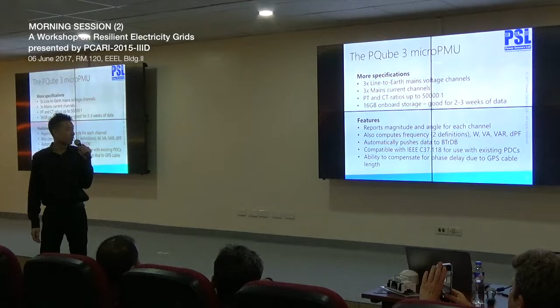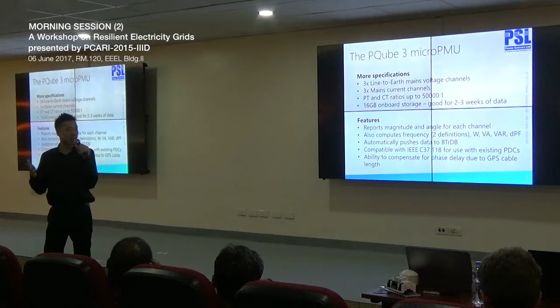Okay, so we have 3 voltage, 3 current. We report magnitude and angle for each channel. We also compute all of the distillates. Basically, these are additional parameters that can be made using the data from one PMU. So we can derive the frequency from the raw phase angle information. There are 2 definitions for frequency in this case. There is the IEEE C37 definition, and then there's another definition that we use, which is simply the first derivative of your phase angle. And then we also compute your real power, apparent power, reactive power, and displacement power factor.